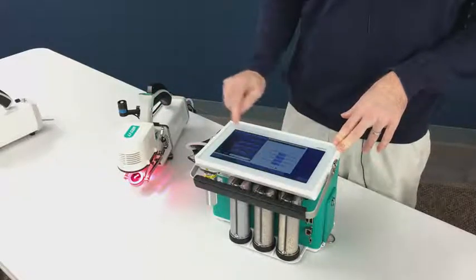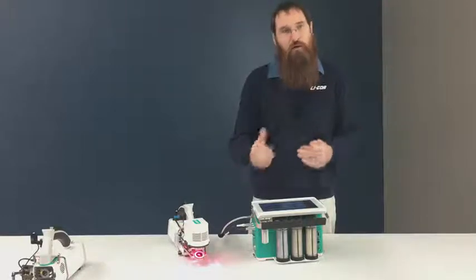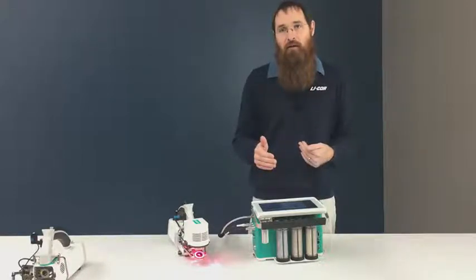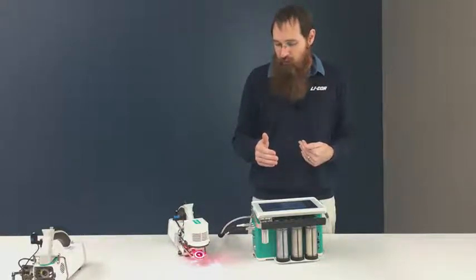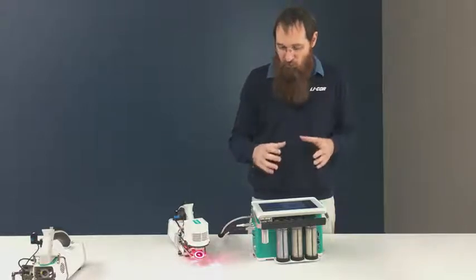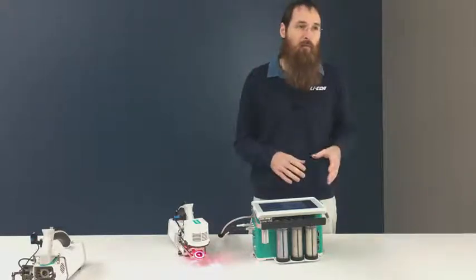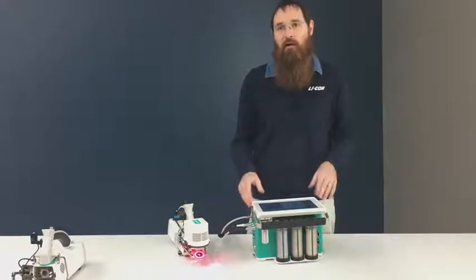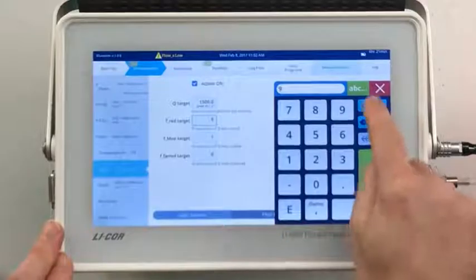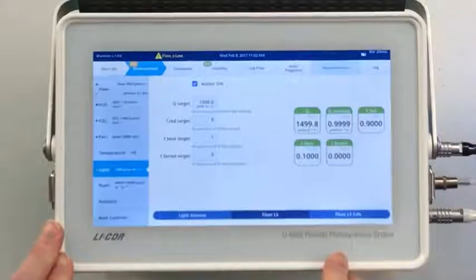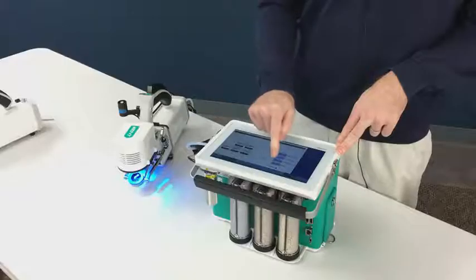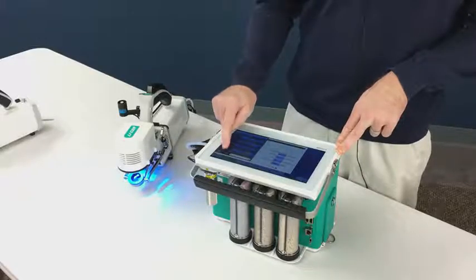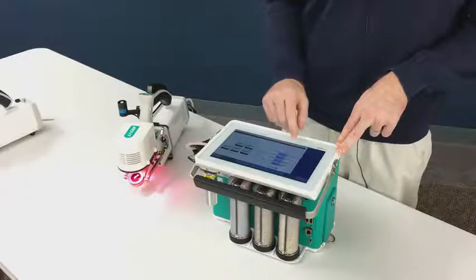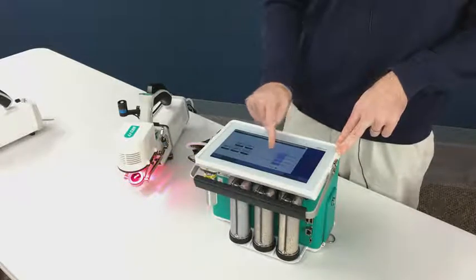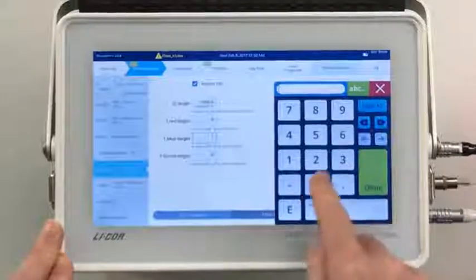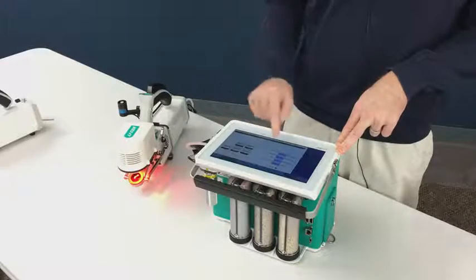I can change my target values, and this lets me proportion red and blue light coming out of the light source. We can do this same proportioning, right? We have independent control of red and blue in both the fluorometer and the 3x3 LED light source now. So if I just clear this and set it to 0, then my light should become all blue. And if I put a 9 back in here, right, by default we would do 90% red, 10% blue. If I just put a 0 in for my blue, my light should become all red.